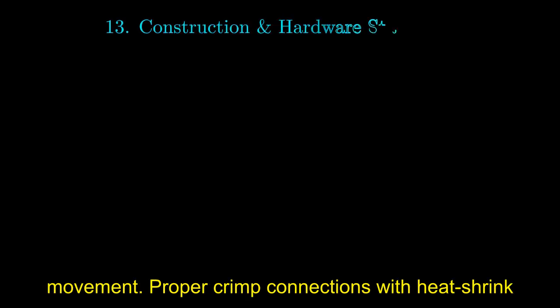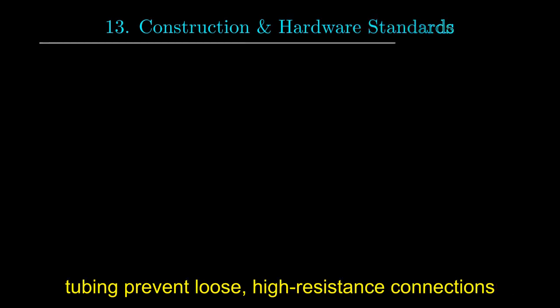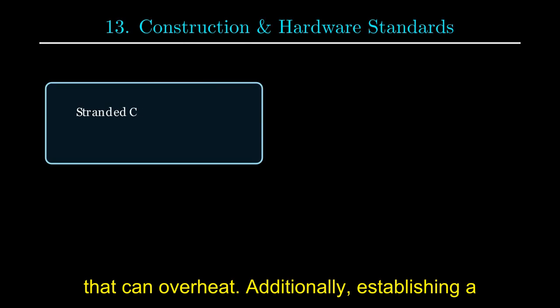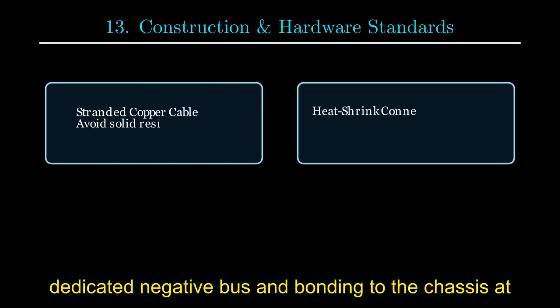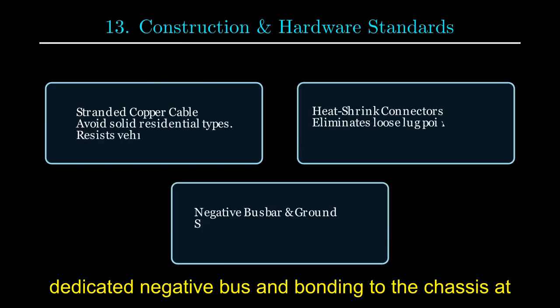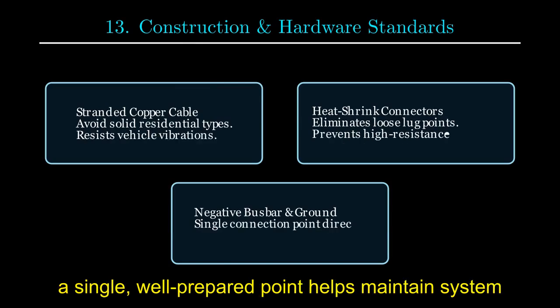Proper crimp connections with heat shrink tubing prevent loose, high-resistance connections that can overheat. Additionally, establishing a dedicated negative bus and bonding to the chassis at a single, well-prepared point helps maintain system integrity.